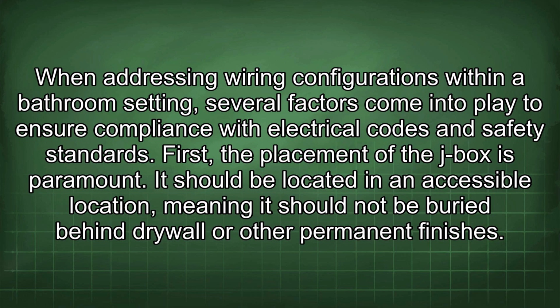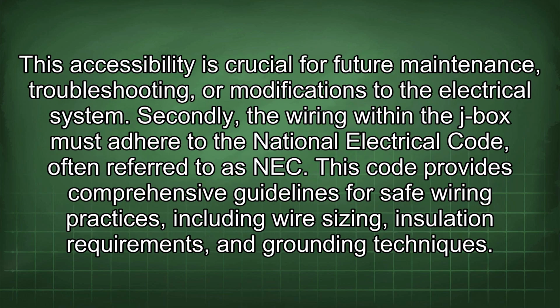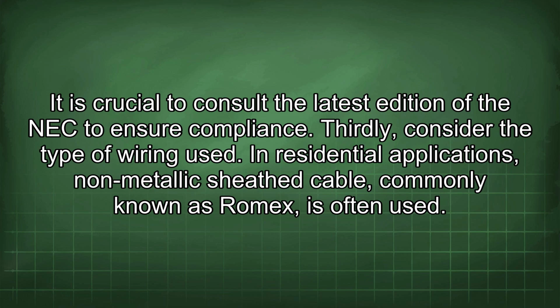It should be located in an accessible location, meaning it should not be buried behind drywall or other permanent finishes. This accessibility is crucial for future maintenance, troubleshooting, or modifications to the electrical system. Secondly, the wiring within the J-box must adhere to the National Electrical Code, often referred to as NEC. This code provides comprehensive guidelines for safe wiring practices, including wire sizing, insulation requirements, and grounding techniques. It is crucial to consult the latest edition of the NEC to ensure compliance.